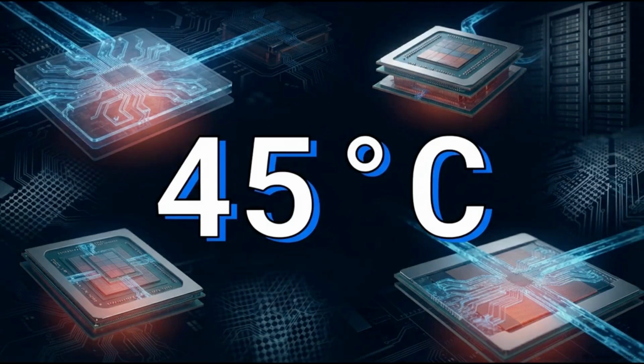But here's the most paradigm-shifting fact about this new technology: the liquid doesn't actually need to be freezing cold. Because the liquid touches the hot silicon directly, the coolant entering the servers can be as warm as 45 degrees Celsius, that's 113 degrees Fahrenheit. That is literally hotter than a hot tub.